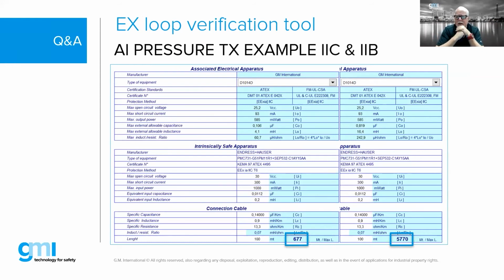And what it's telling us, and what you see here, which is kind of interesting, down at the very bottom, you notice that depending on the particular product, and depending on the potential gas group, because a lot of the parameters are actually the same, because we're using the same barrier, you notice that in one case, the length of cable is limited to 677 meters, but in the other case, we can use a cable length of up to 5,700 and so forth meters.